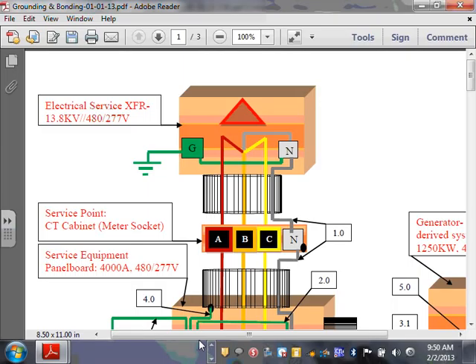Okay, so now, what do you do here in this box? Typically, we bring the neutral. Do we have to bond and ground? Do we have to drive a grounding conductor? You can if you want to. We are on what's called the line side of the service disconnect means. On the line side of the service disconnect means you're allowed to ground the equipment using the neutral, but use it sparingly. That's what the code says.